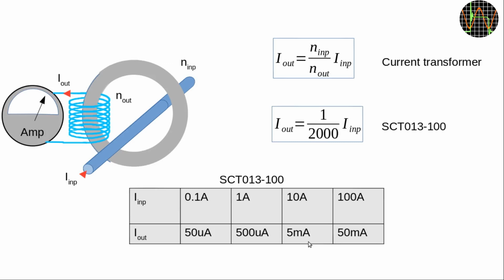If that seems too troublesome, you can loop the to-be measured wire so it goes twice through the core. The primary winding is now 2, which means in accordance with the formula, the ratio is now 1 to 1000, and 10 amps in the primary causes a current of 10 milliamps in the secondary. Very straightforward and easy. But of course, the maximum current you can measure with this transformer is now halved from 100 amps down to 50 amps.